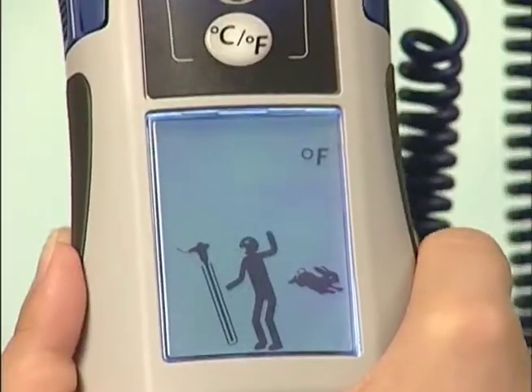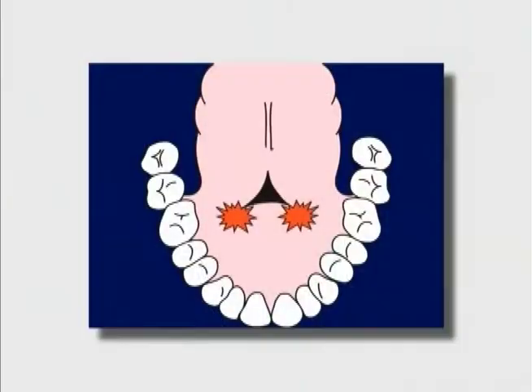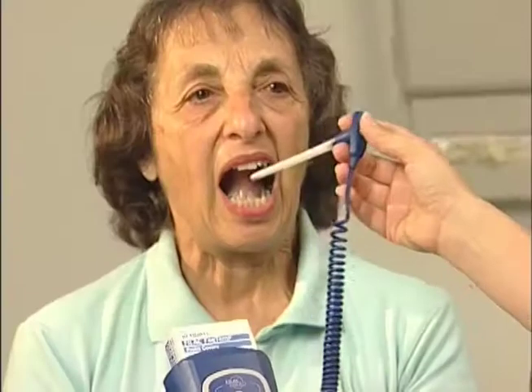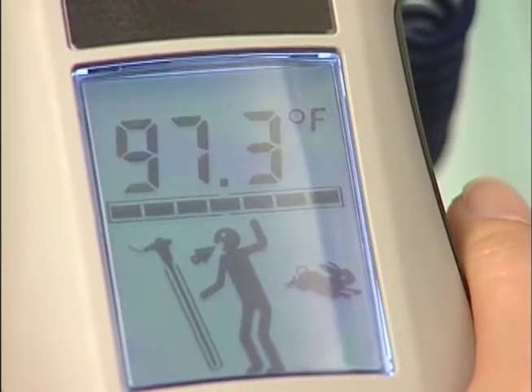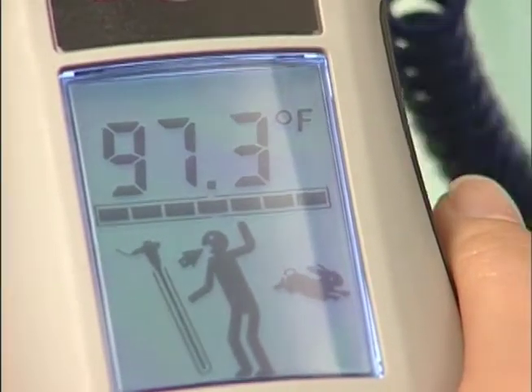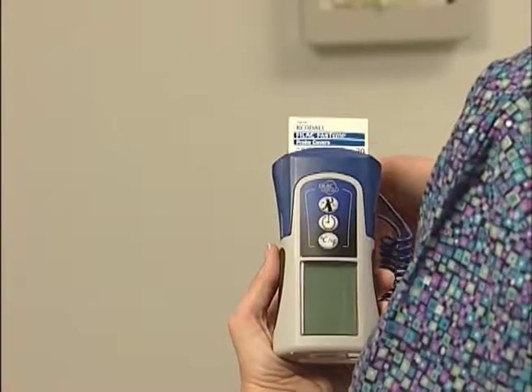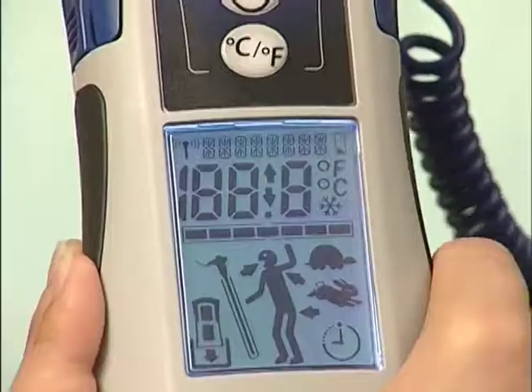Insert the probe tip deep into the sublingual pocket next to the frenulum linguae, which is the vertical fold of tissue centered beneath the tongue. The tip may be placed on either side of the frenulum linguae, toward the back of the mouth. This location is considered a heat pocket, and the probe must be placed and held there to obtain accurate temperature readings. Ensure that the patient's mouth is completely closed. Hold the probe in place until a long beep sounds, indicating the temperature measurement is complete and the final reading is displayed.